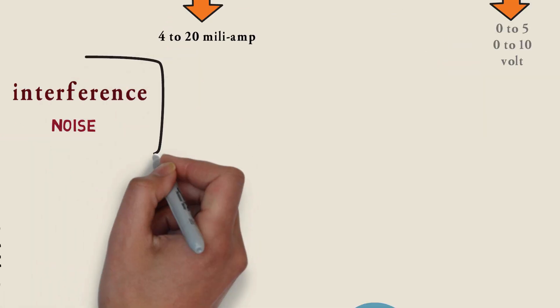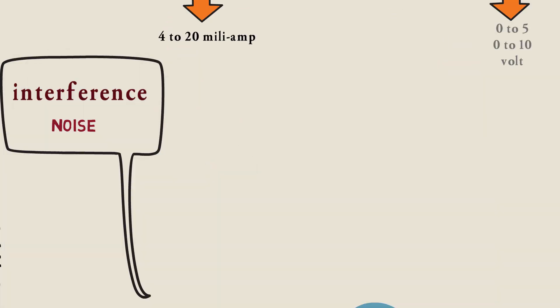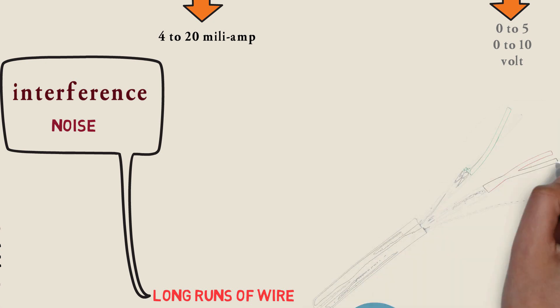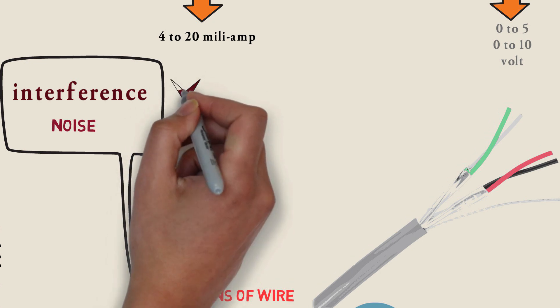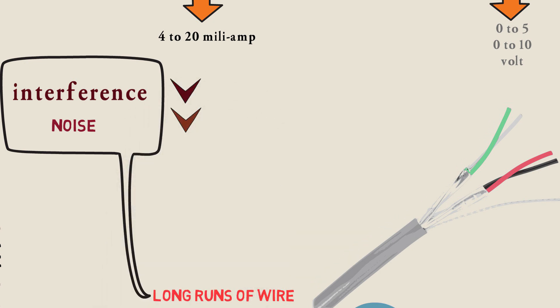Due to interference and noise, which can affect significantly long runs of wire, we want to make sure with analog signals that we use a twisted and shielded pair. This will help us reduce the interference and the noise with analog signals.